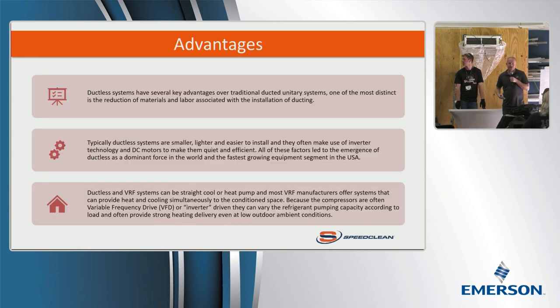A lot of key advantages to ductless—one of the biggest being you don't have as much labor and material in installation because you don't have ductwork. Even with what we call a ducted mini-split—mini-split and ductless are kind of used interchangeably, sometimes I even say 'ducted ductless,' which makes no sense—but even those systems generally have really short duct runs. So you're able to put the unit in a location you wouldn't traditionally put an air handler, like pancake units or low-profile compact units, fitting them above a ceiling space and running a shorter duct.